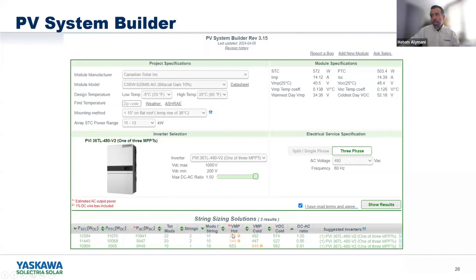But the most important thing here to look at is the VMP hot and VMP cold. You don't really want to see anything with a warning sign on those two columns. Of course, for VOC, we're not going to recommend anything that will exceed 1,000 volts. So you'll see all these values below 1,000 volts. But when it comes to VMP cold and VMP hot, these warnings mean that the maximum power voltage for the string is actually either lower or higher than the maximum power voltage of the inverter.